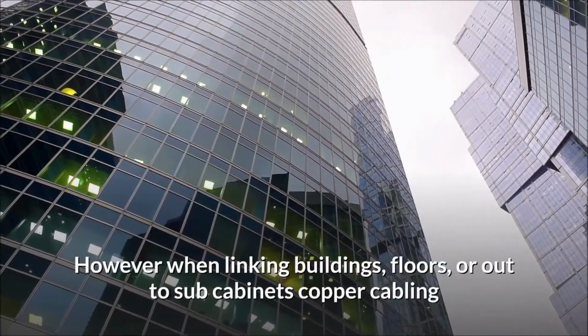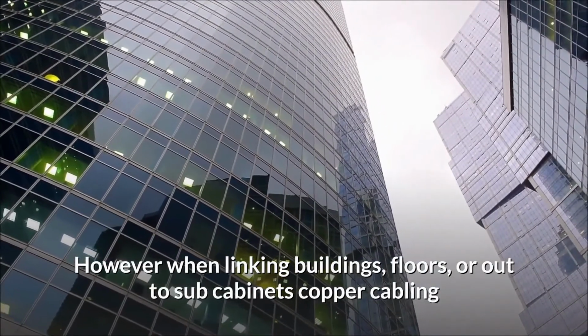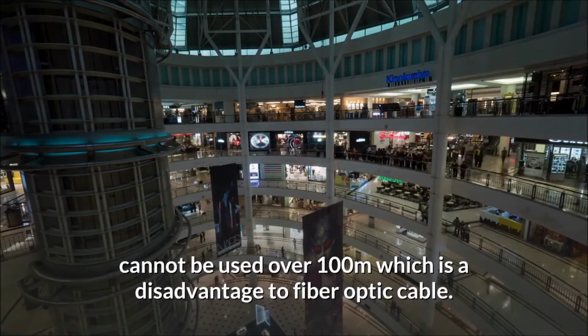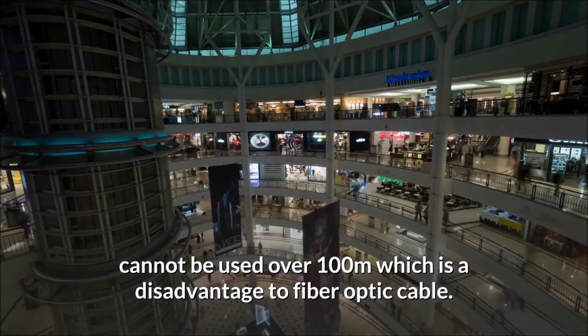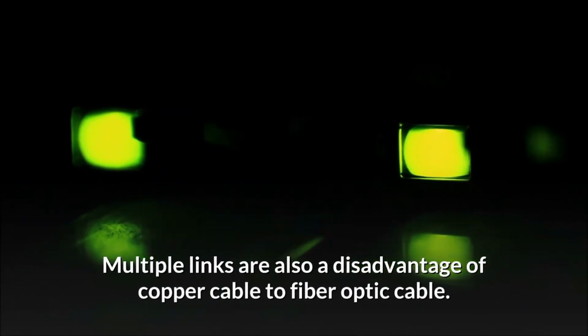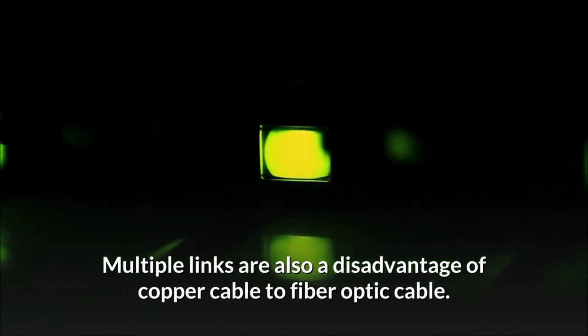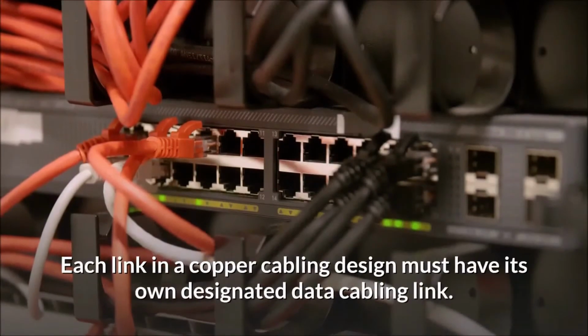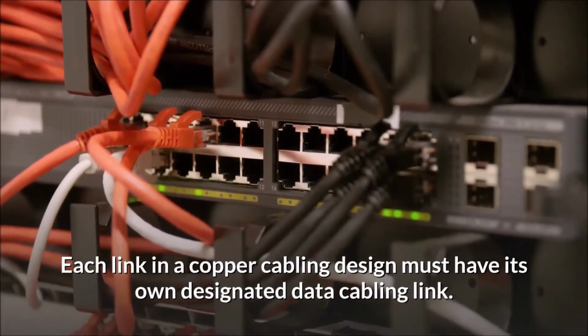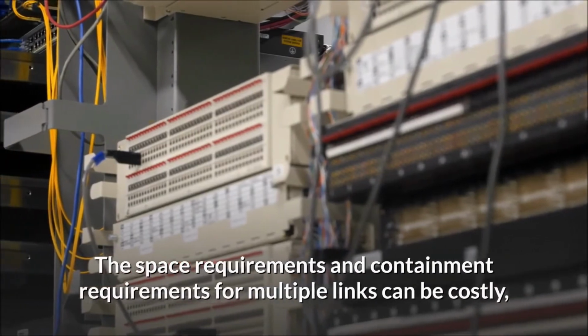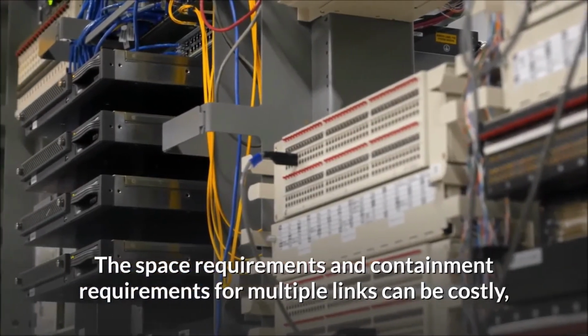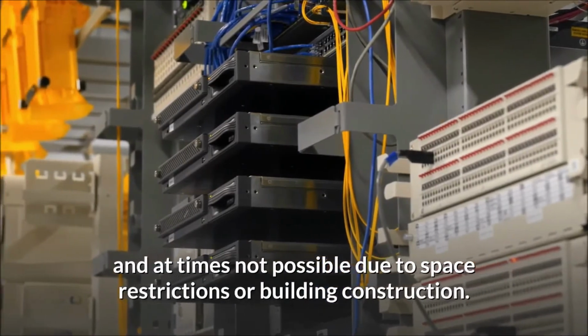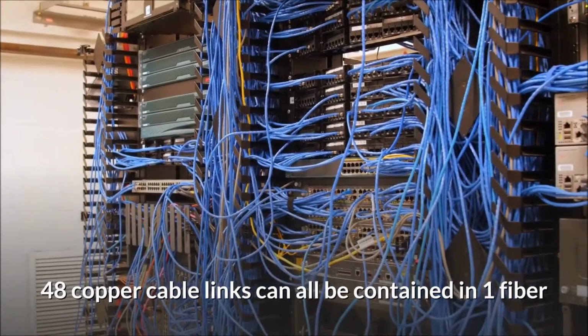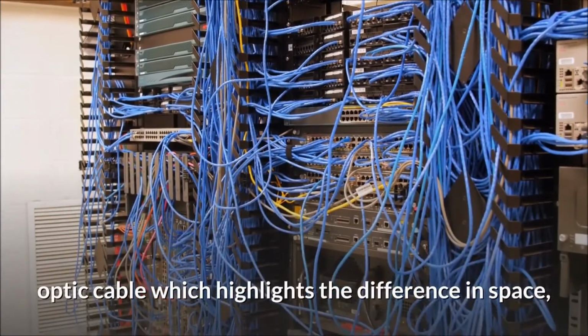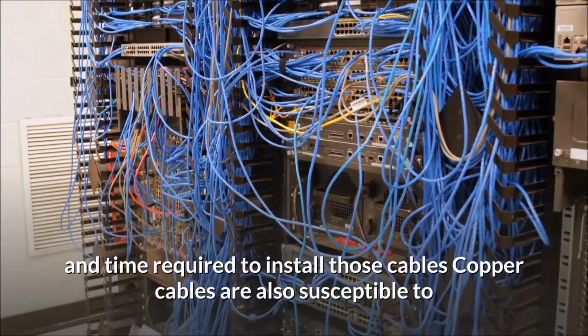However, when linking buildings, floors, or out to sub-cabinets, copper cabling cannot be used over 100 meters, which is a disadvantage compared to fiber optic cable. Multiple links are also a disadvantage of copper cable compared to fiber optic cable. Each link in a copper cabling design must have its own designated data cabling link. The space requirements and containment requirements for multiple links can be costly, and at times not possible due to space restrictions or building construction. 48 copper cable links can all be contained in one fiber optic cable, which highlights the difference in space and time required to install those cables.